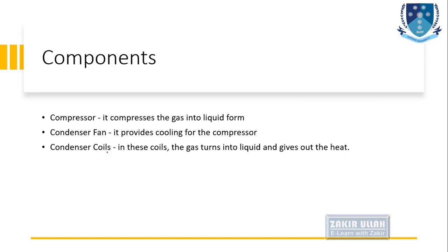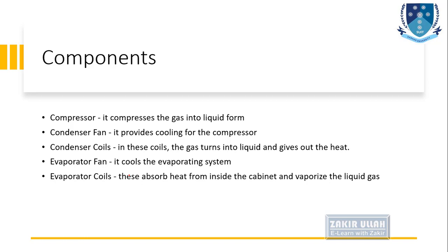And the condenser coils: in these coils the gas turns into liquid and gives out the heat to the external environment. Then an evaporator fan, which cools the evaporating system of the cold incubators. And evaporator coils: these coils absorb heat from inside the cabinet and vaporize the liquid gas.